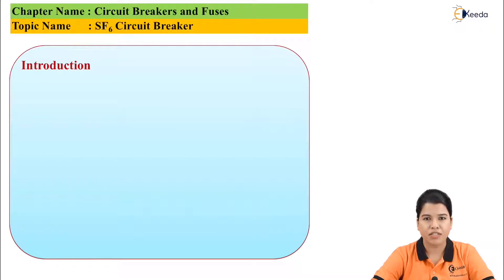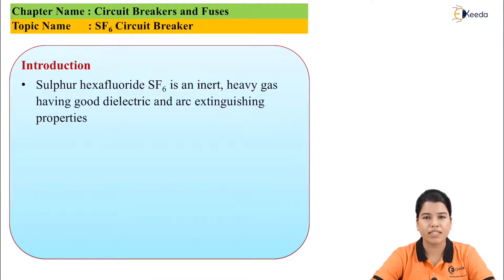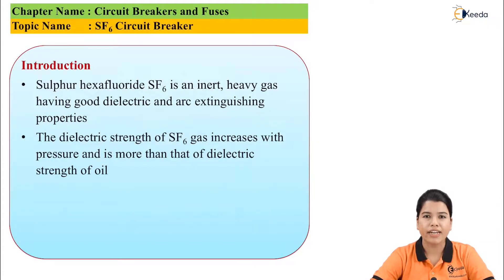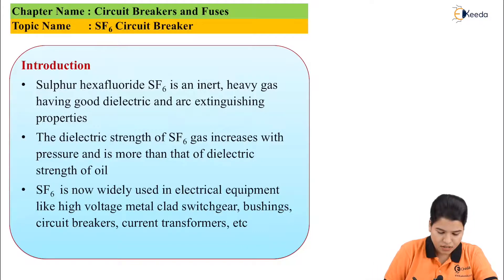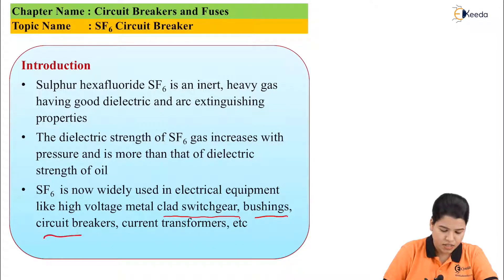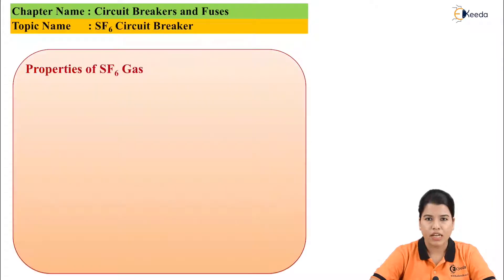The SF6 circuit breaker basically uses SF6, that is sulfur hexafluoride gas, which is inert in nature and has a very good dielectric strength. As the pressure increases, the dielectric strength of the sulfur hexafluoride gas also goes on increasing, which assists in arc quenching. Because of the properties of SF6 gas, it is nowadays widely used in various types of switchgear devices for the protection of metal clad switchgear, bushings, circuit breakers, and current transformers.